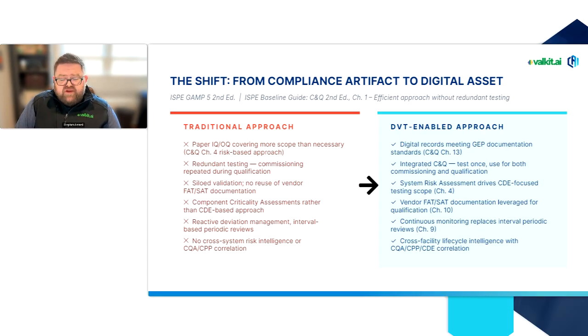The right column is where the ISPE baseline C&Q guide lands, and this is not a technology pitch—these are capabilities described in the guidance itself. Digital records that meet good engineering practice standards, integrated C&Q where vendor documentation is leveraged for qualification rather than duplicated, system risk assessment outputs that scope your testing to critical data elements, and continuous monitoring that replaces the snapshot approach of interval-based periodic review.